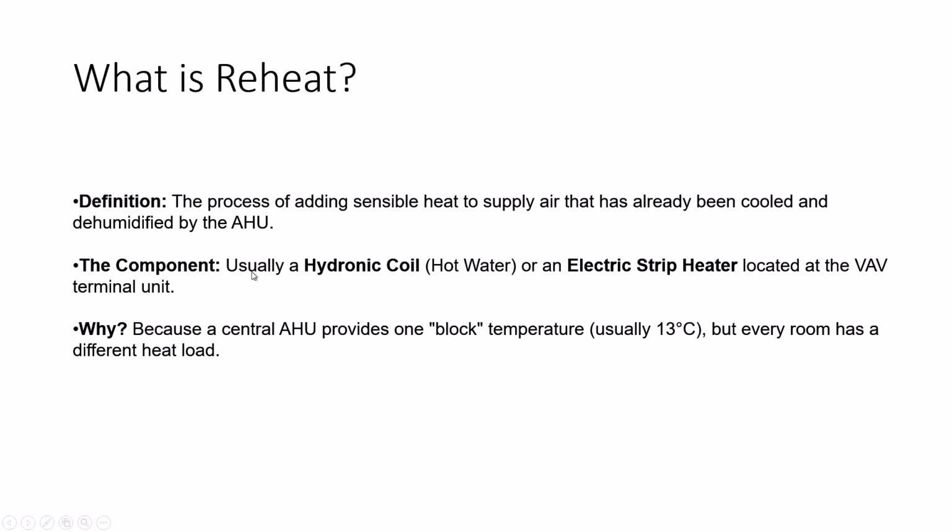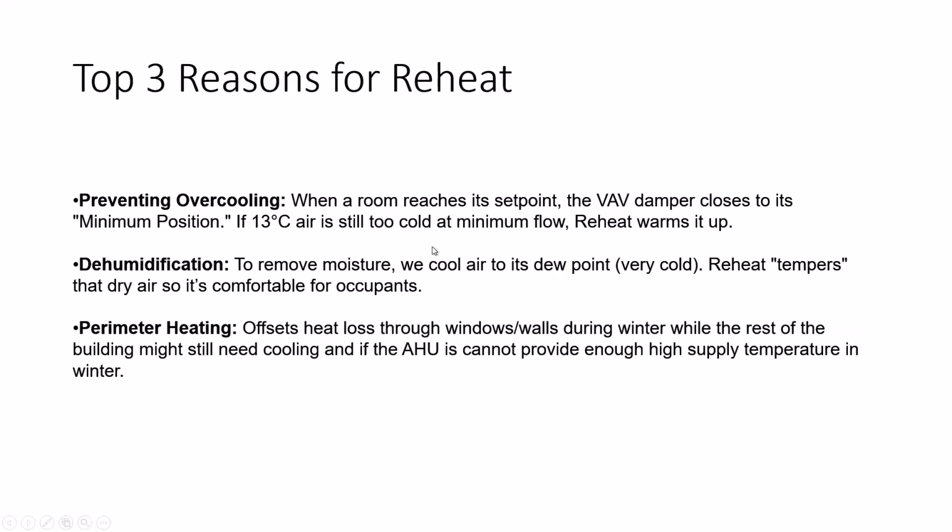Usually a hydronic coil, hot water, or electric strip heater is used for reheat. A central AHU or RTU provides one block temperature, usually 13 centigrade or 55 Fahrenheit, but every room has a different heat load. So we need to provide different supply temperatures to the space. That's why we need reheat.